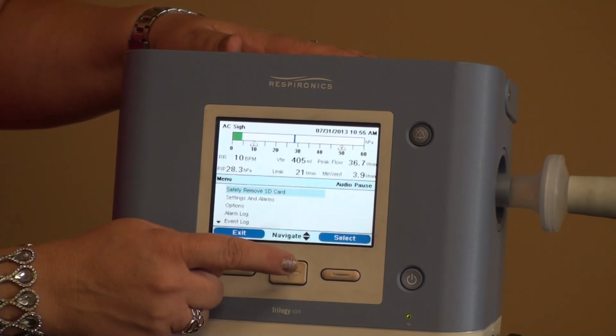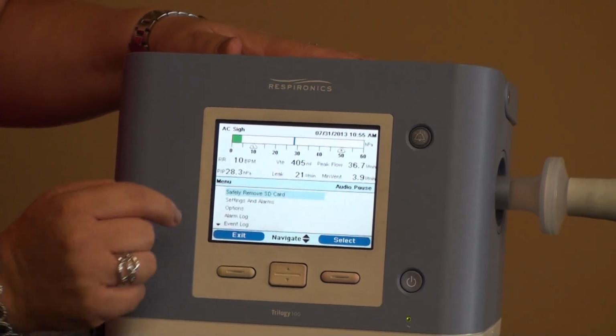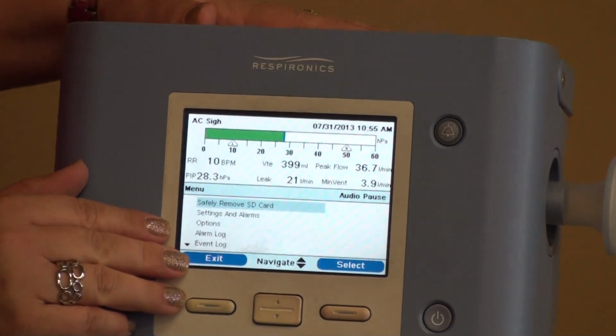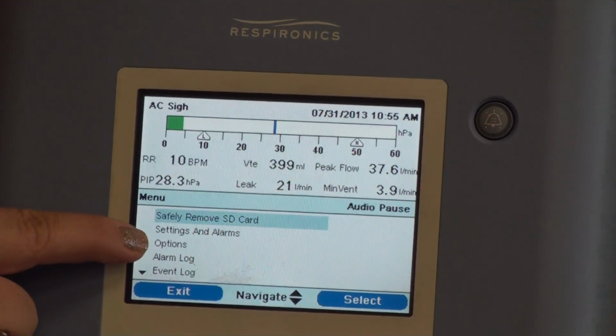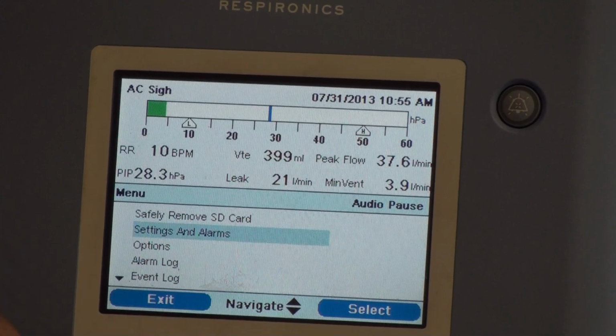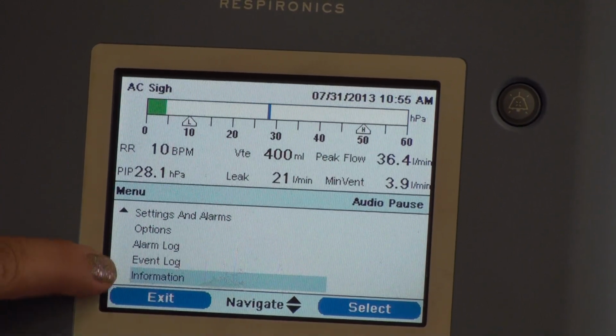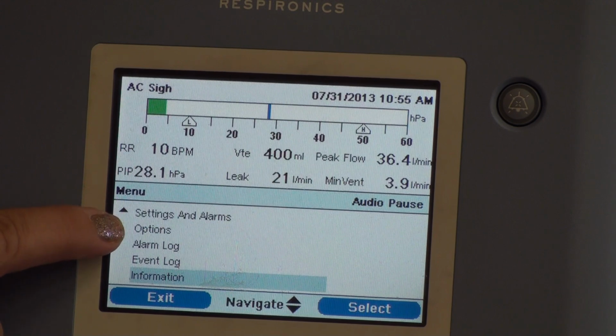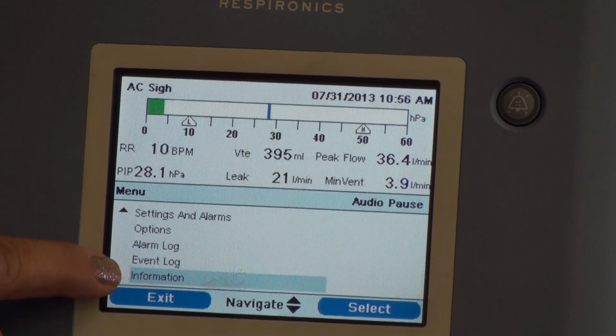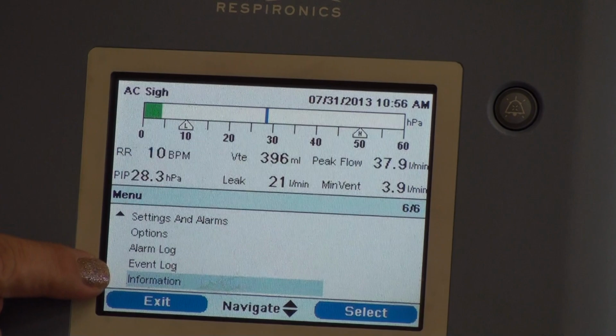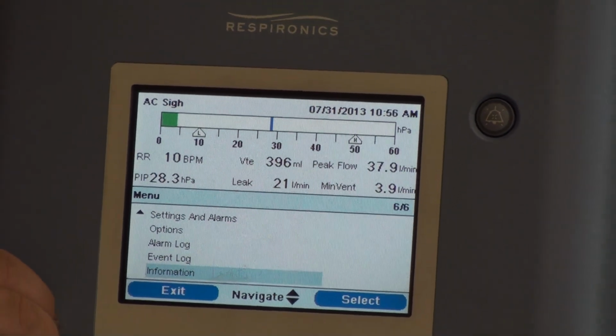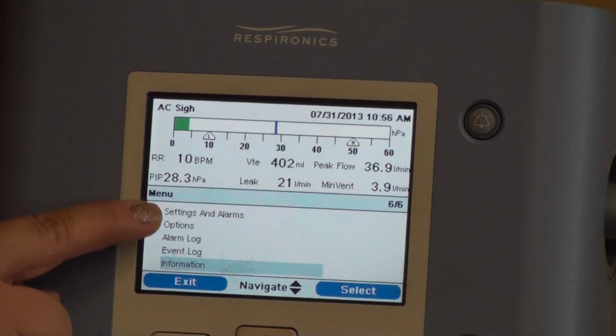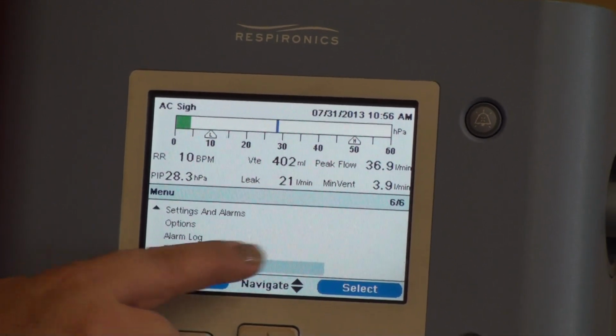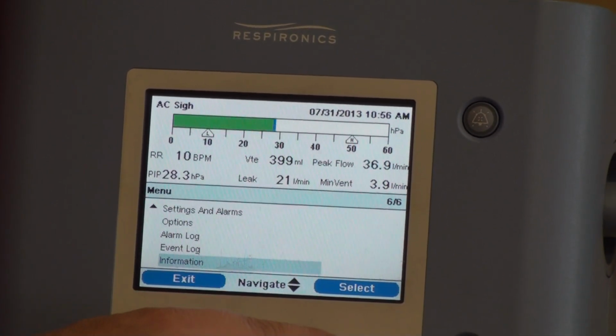So if I want to go in, I press the up toggle. Then this screen comes up. The three things I'm going to want to know on this screen are my settings and alarms, my options, and if I go down one, my information. Settings and alarms, options, and information are the three things that I will deal with mainly. Not that the other ones aren't important, and you can look through them and everything, but those are the three I will deal with. When I am doing my vent check, I will go into information. So I'm going to toggle down until it highlights information, and I'm going to select it because I want to go in there.